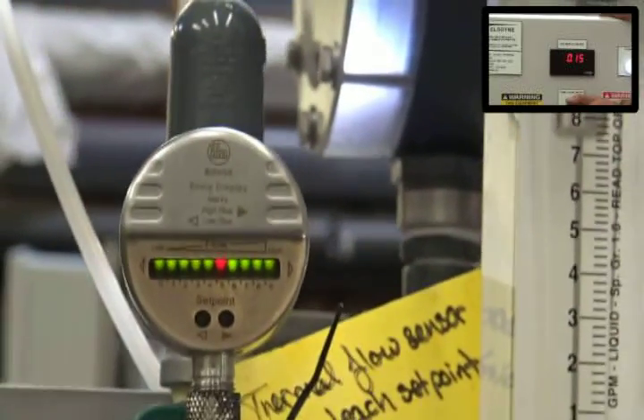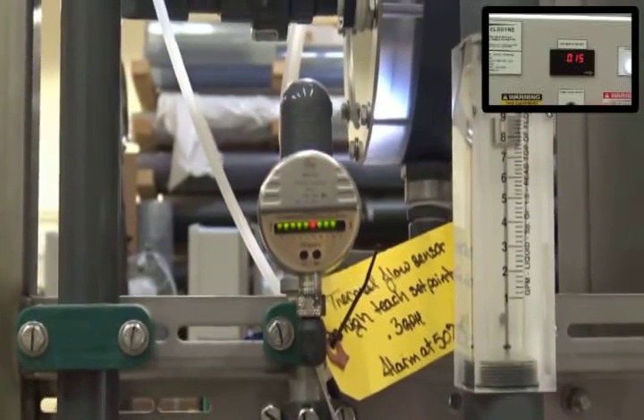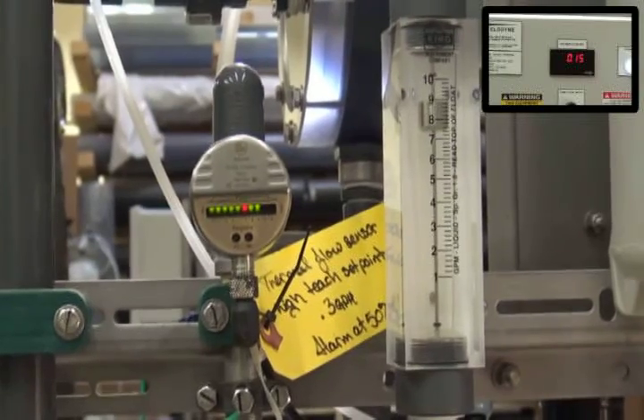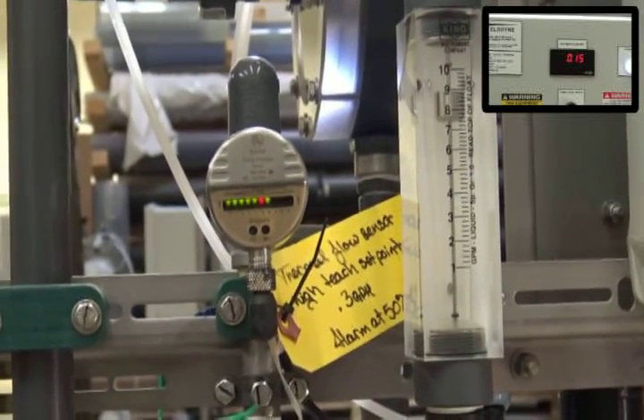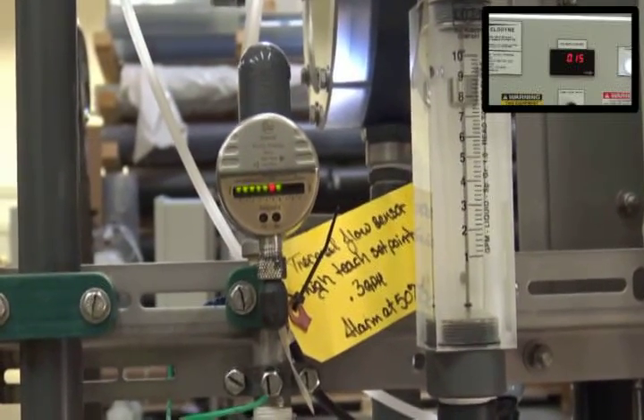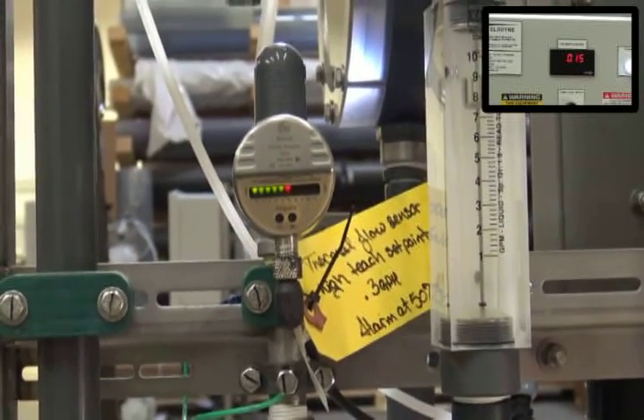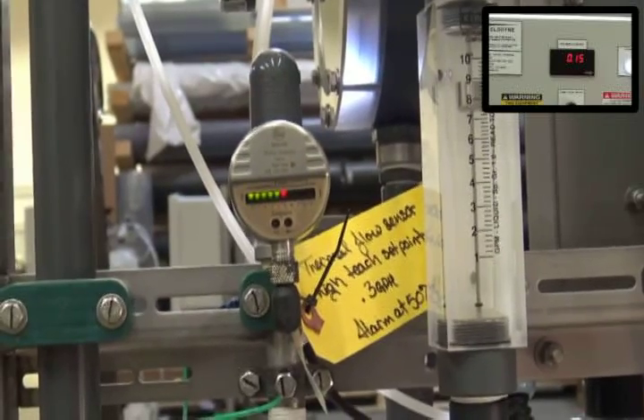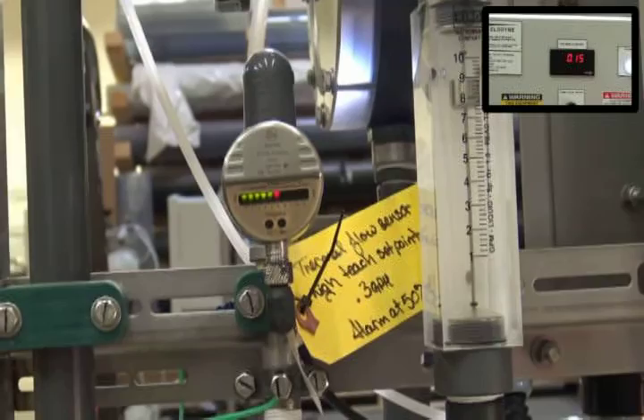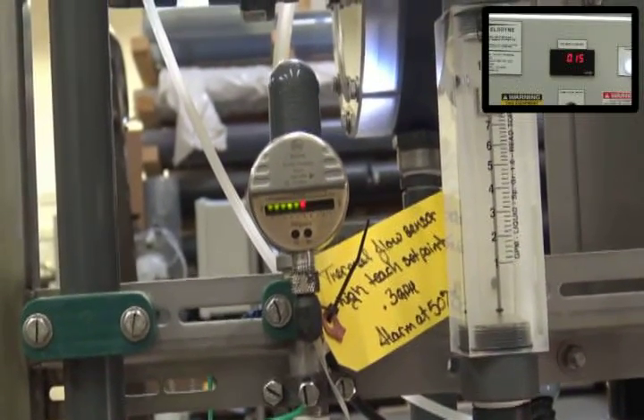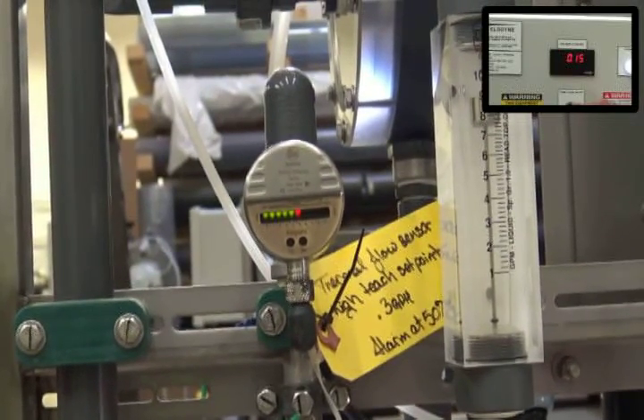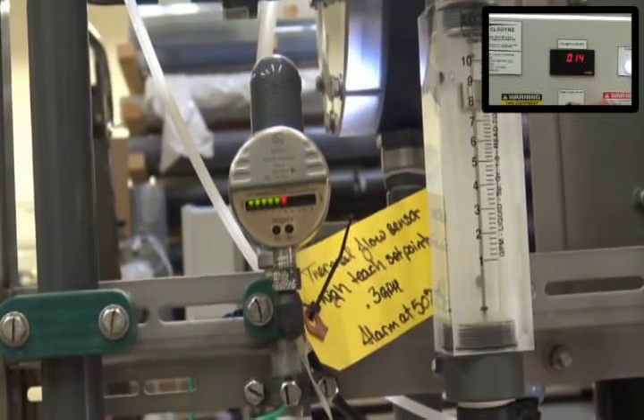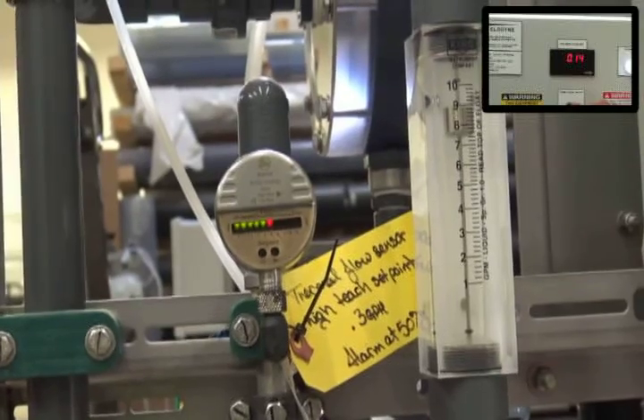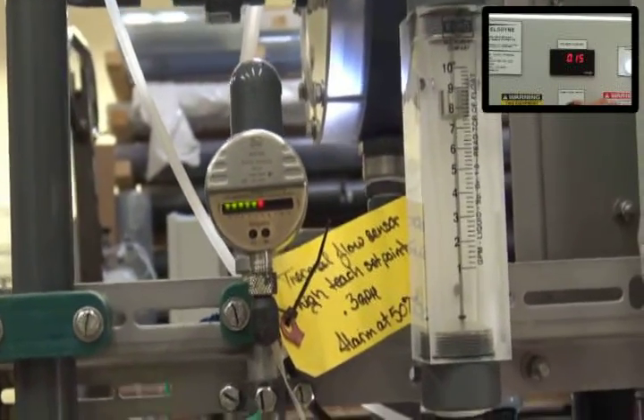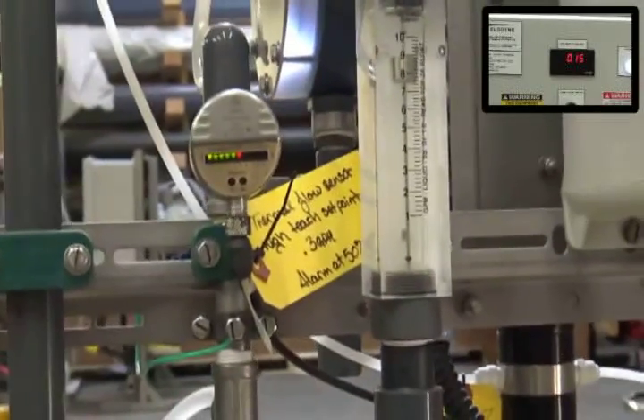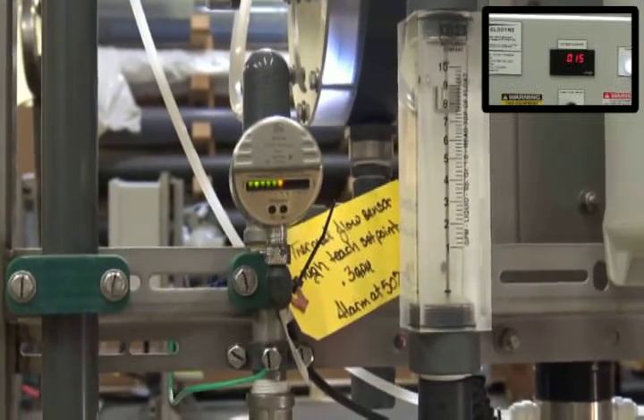And if you notice, the lights will start disappearing, and it'll get down to about where the red light is, and the red light should turn orange, and then it kind of just hangs out for a while. Now, normally this would alarm right when the light turns orange, so you wouldn't be able to experience it just hanging out in the center there. Maybe. Wow. Now this is a good opportunity to, there we go, now it's orange. So that would have normally shut your system down and you would have gotten an alarm.